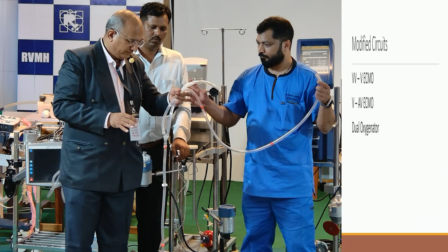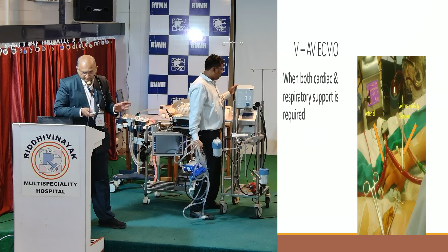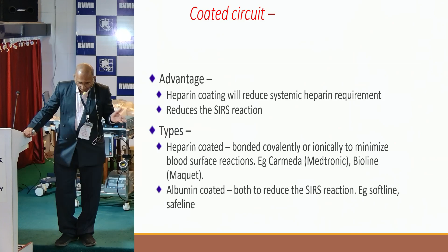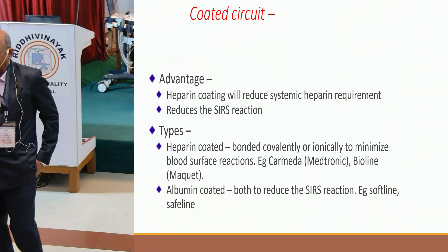Now most of the time you have a flow sensor which is detachable, so you can connect it. Usually we connect it to the return line, and there is one direction which is given on the flow sensors. You can see the directions. So you have to connect the flow sensor in that direction. Otherwise it will measure negative pressures, and the moment it measures negative pressures, the pump stops. So you have to be mindful about this. There is a direction given, so you have to connect it in the same direction.